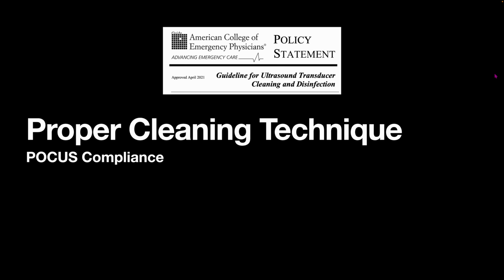Now, proper cleaning technique is not specific to any one specialty. This guideline for ultrasound transducer cleaning and disinfection that I'm going to speak about comes from the American College of Emergency Physicians, but the information here, again, isn't specific to emergency medicine. This actual information comes from the American Institute of Ultrasound in Medicine. The Society of Hospital Medicine, if they do have a guideline for transducer cleaning and disinfection, will undoubtedly be the same exact information. Cleaning standards are set by the manufacturer, but requirements vary by institution.